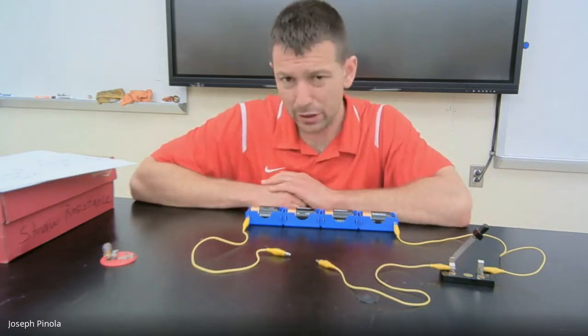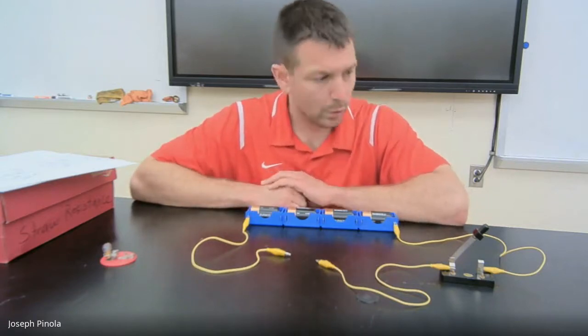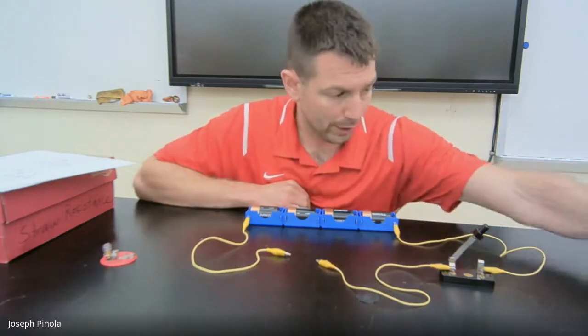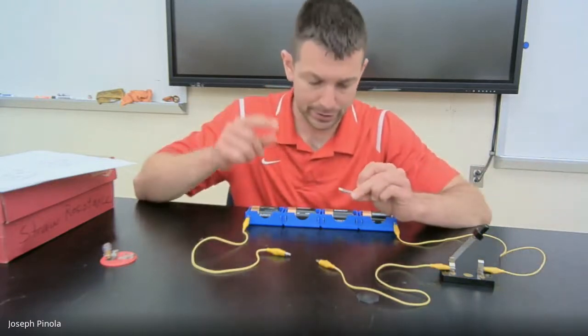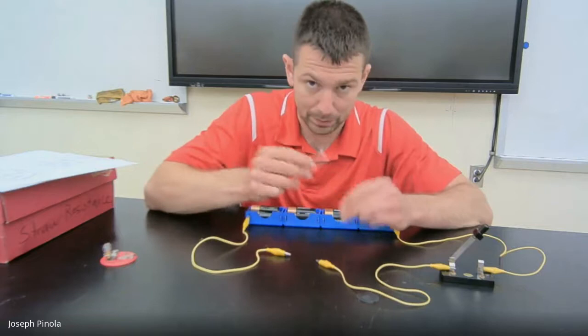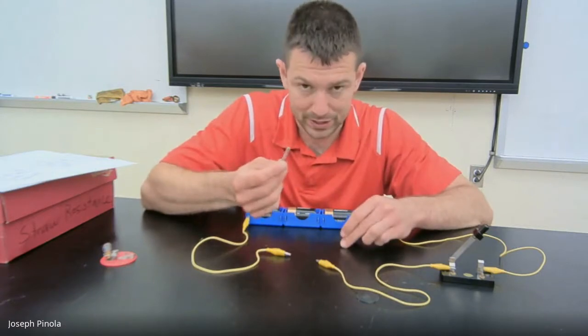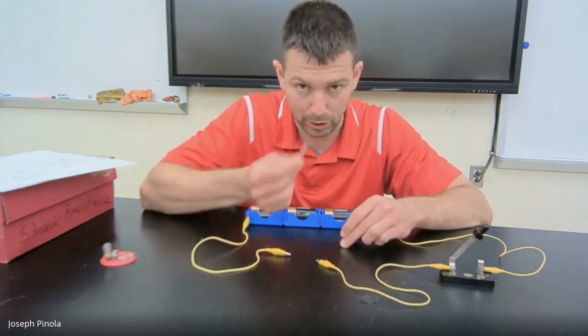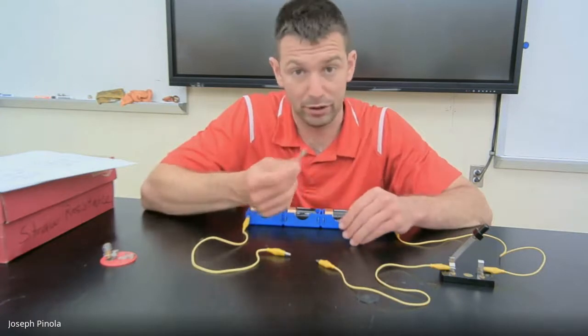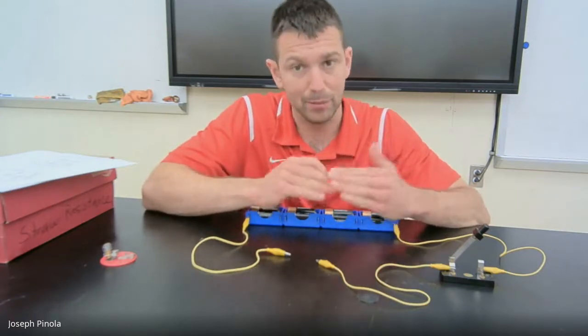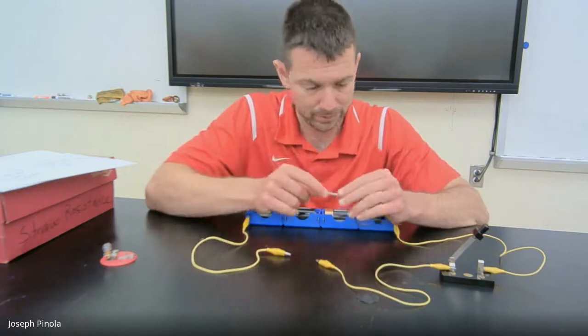If we think the problem has been fixed, we can replace the fuse with another one that has a little bit of a higher tolerance. This fuse, for example, goes up to 20 amps. That means it can handle much more current, and it will only burn out if the current goes above 20 amps. There's a lot more flexibility with a fuse like this.